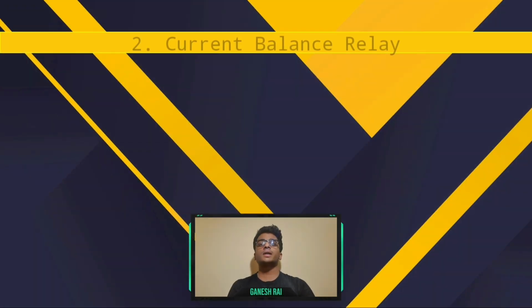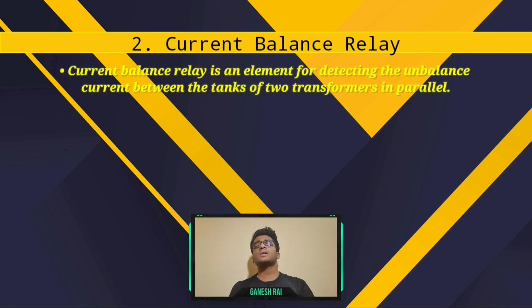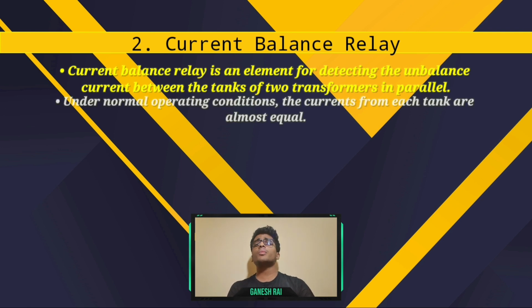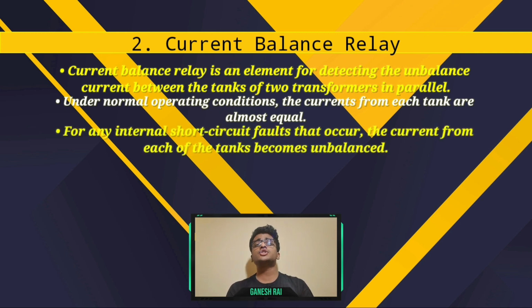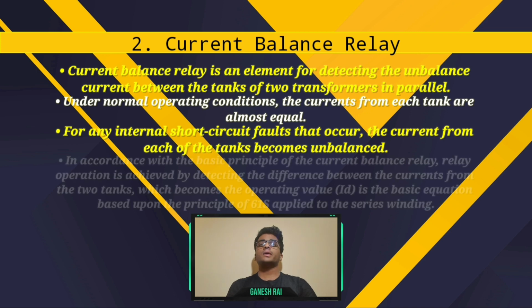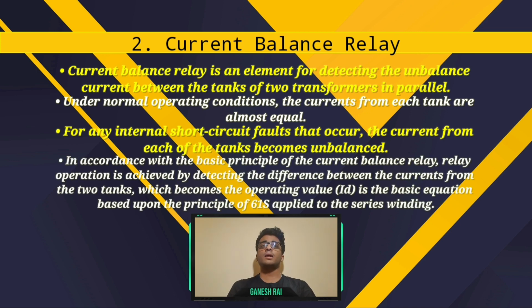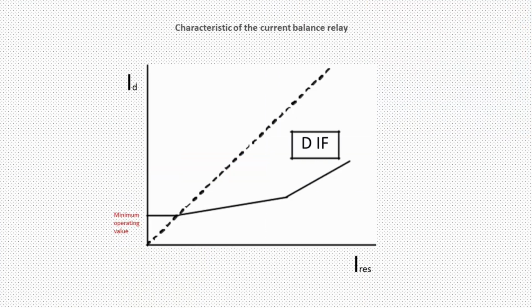Now talking about current balance relay. Current balance relay is an element for detecting the unbalanced current between the tanks of two transformers in parallel. Under normal operating conditions, the currents from each tank are almost equal. For any internal short circuit faults that occur, the current from each of the tanks becomes unbalanced. In accordance with the basic principle of current balance relay, relay operation is achieved by detecting the difference between the currents from the two tanks, which becomes the operating value ID. It is the basic equation based upon the principle of Kirchhoff's law applied to the series winding. This is the characteristic graph of ID versus IRES.